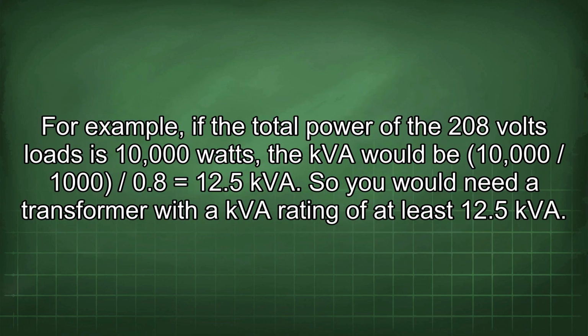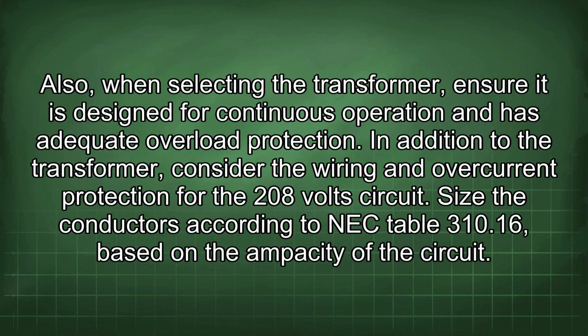For example, if the total power of the 208 volt loads is 10,000 watts, the kVA would be 10,000/1000/0.8 equals 12.5 kVA. So you would need a transformer with a kVA rating of at least 12.5 kVA. Also, when selecting the transformer, ensure it is designed for continuous operation and has adequate overload protection.